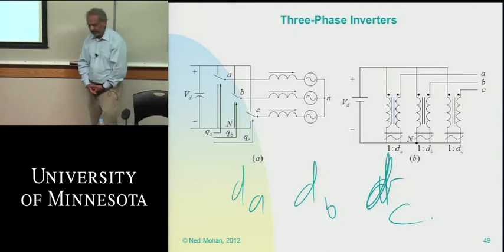If you apply that to a wind generator, what do we see here? We have this variable frequency voltage coming from the generator, and we have the grid over here. We have three switching power poles on this side converting this variable frequency, variable amplitude voltage to a DC voltage. And again three switching power poles taking this DC voltage, chopping it up at some very high frequency, creating AC voltages at these points to transfer P and Q. By controlling the phase angle of the voltages generated here compared to the grid voltages, we can control the real and reactive power.